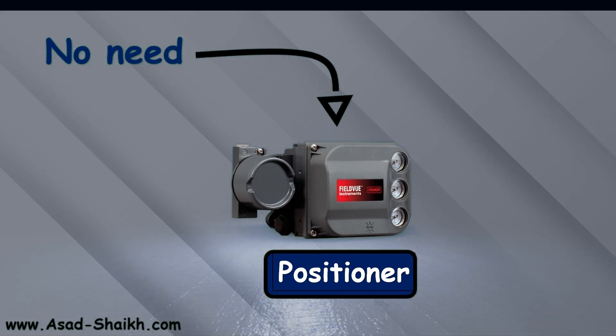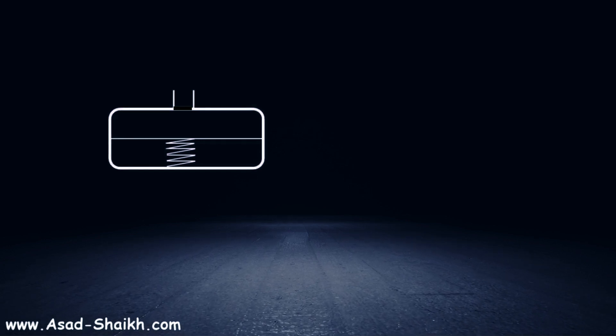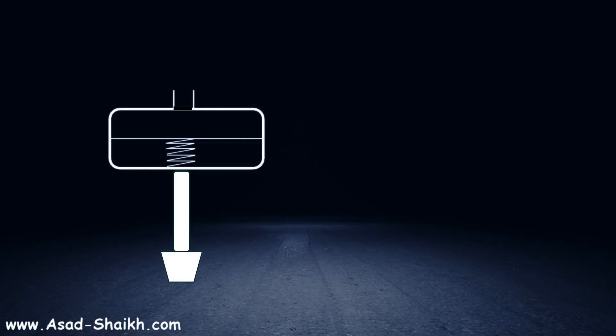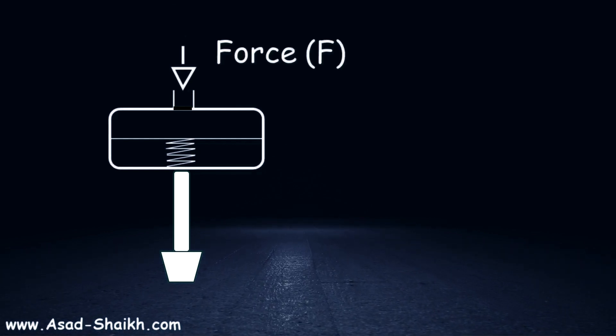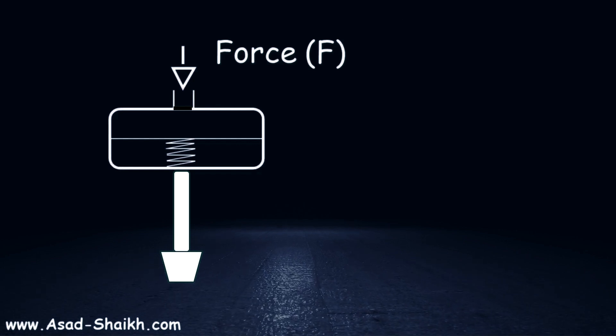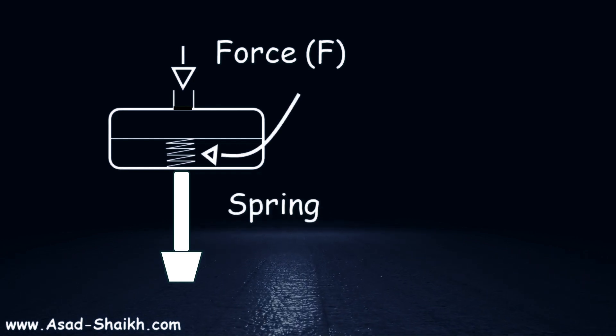We'll understand with the help of Hooke's Law. Imagine that we have an actuator assembly here which is connected to our plug and seat assembly. The force will come from the upper direction because it is an air to open valve, so the air pressure force will come here and that will basically have displacement of the spring, let's call it x.